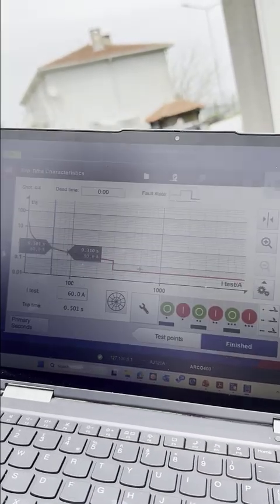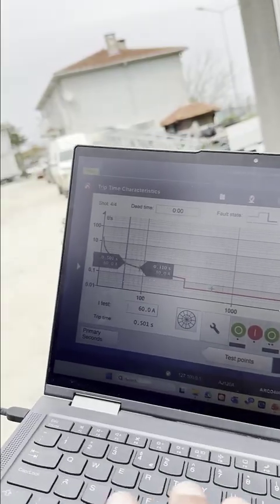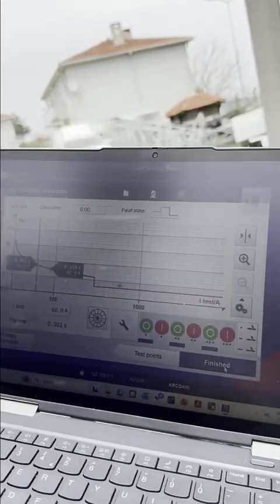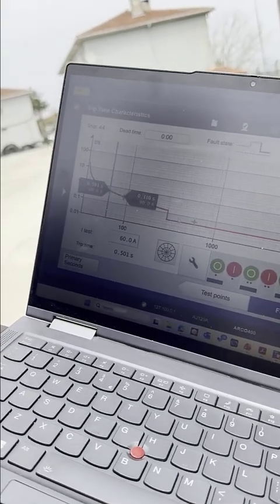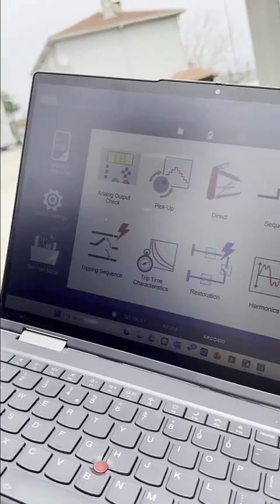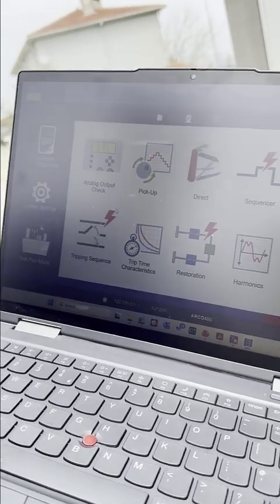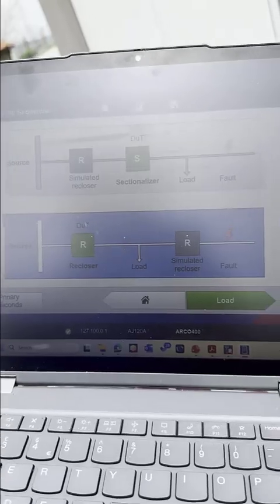Then you can append. Okay, so now we tested the first and second stage, the two stages of the overcurrent protection in IEC normal inverse and definite time. Then you can click finish. The last one, we can now test the tripping sequence. Now you can select from different modes, the recloser or sectionalizer. If you select sectionalizer, it will be simulated.